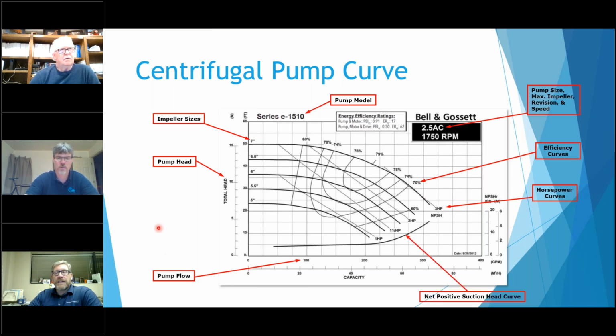And this is your net positive suction head curve. It's a little bit easier to see on this one because it's a little bit bigger, but out here's your scale for it. If it's a cooling tower application and you're at 200 here, you come over, and it's only 5 feet that you need, which is about 2 pounds of suction pressure, which isn't too terribly much.